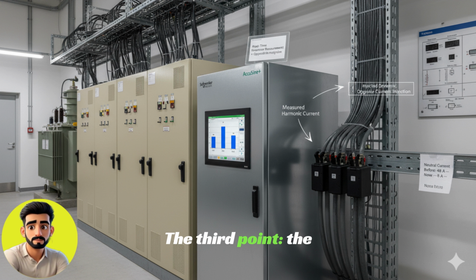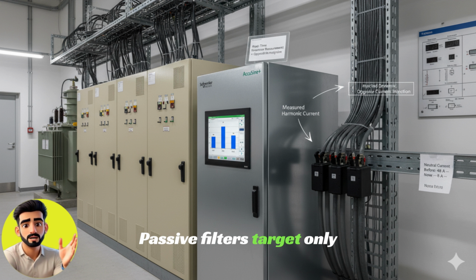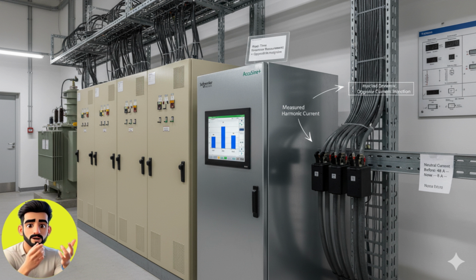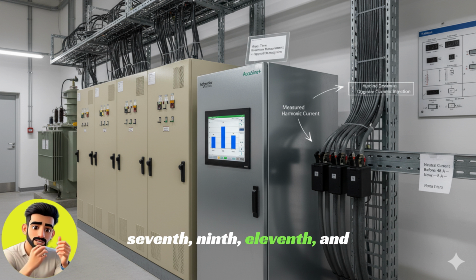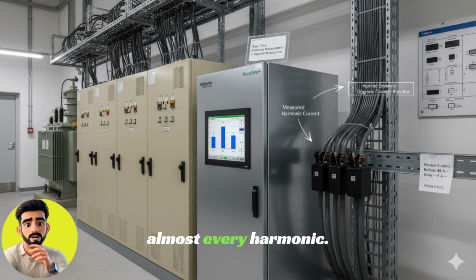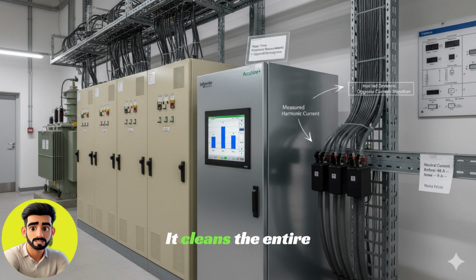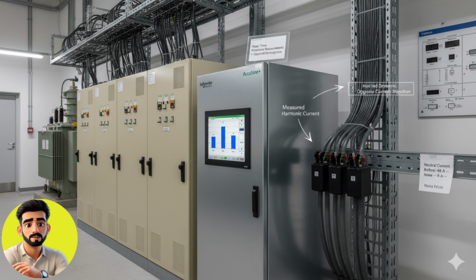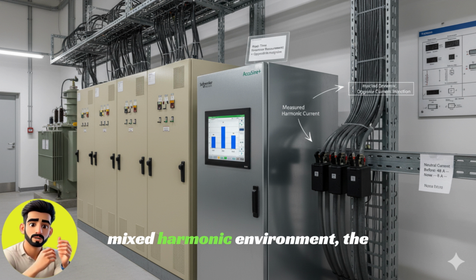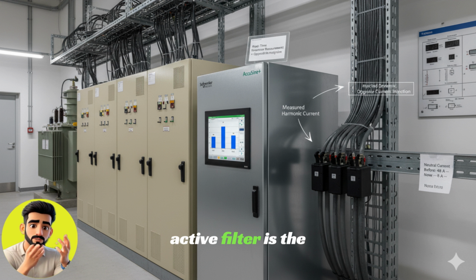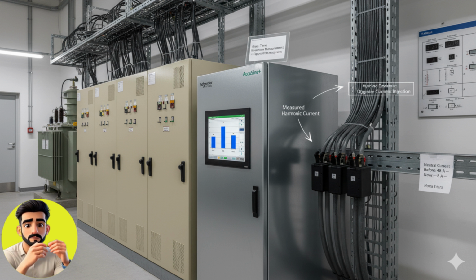The third point, the active filter works on multiple harmonics. Passive filters target only the fifth or seventh harmonic. But the active filter can target the fifth, seventh, ninth, 11th, and almost every harmonic. It cleans the entire system, not just one harmonic. That's why, in a mixed harmonic environment, the active filter is the most powerful solution.